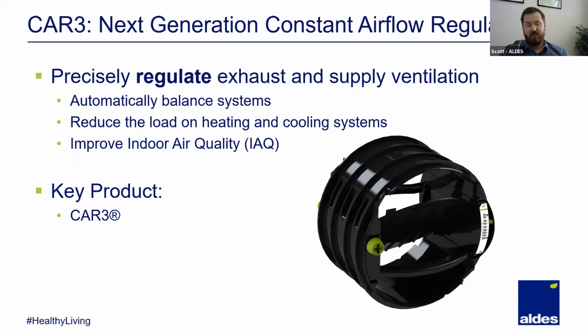So the purpose of the constant airflow regulator is to balance, right? The easiest way to think of this device is it's a balancing damper, but it's automatic. So instead of having a manual balancing damper where you have to take an airflow measurement and then make a manual adjustment to an OBD or maybe an iris damper or something along those lines, this device, you can order it factory set at a specific CFM, or you can field adjust it and slide it into the duct or install it as part of an assembly. And as the pressure within the system changes, it's going to automatically adjust itself to maintain that set airflow. So it's an automatic balancing damper.